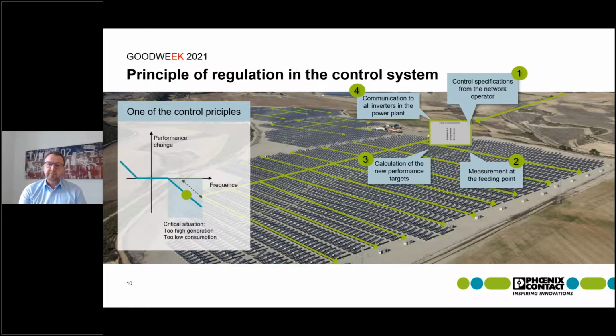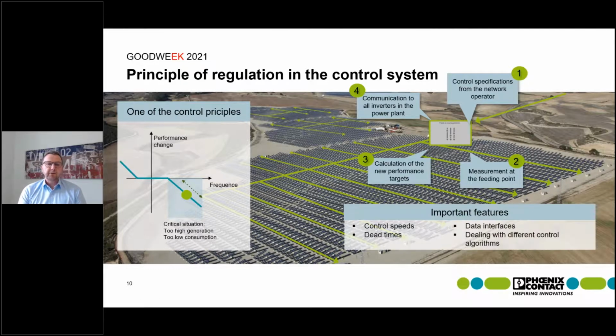To give a more detailed insight into the functionality, you have to consider some important features. The important feature is the control speed, because you have to react very fast at the grid connection point. Yet you broadcast the information to the different inverters, the inverters reduce the power, and you measure the power again. In this control loop you will have dead times or delay times, which have to be considered.